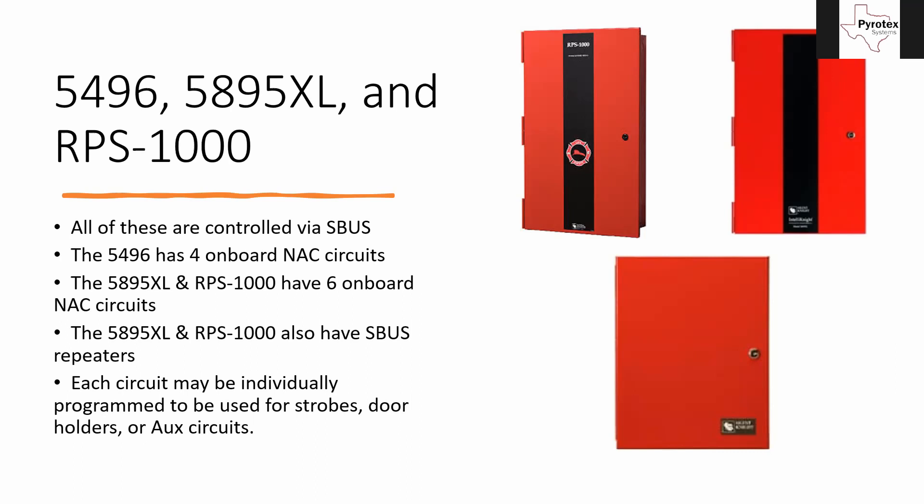My advice for when installing these larger panels: anytime you have SBUS coming in and out, utilize that repeater so you never have to worry about it. The stronger the signal is, the faster everything communicates and the better it'll be for the system. Even if you've only got six of these panels and you do it at five of them — because one has to be the end — it might be overkill, but it's not going to hurt; it's overall good for the system.